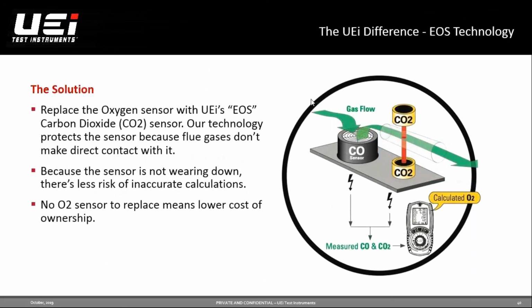So UEI decided there's got to be a better way to do this. Once again, you need two values, and you can extrapolate out the third. So UEI's engineers, who are way smarter than I am, came up with this idea called our EOS technology, our electrical optical sensor. What that does is give you a direct reading of the CO, then it takes the rest of the gases and passes it through a bit of an IR bench to give you your CO2 reading, and then it calculates out the oxygen. Now that's allowed us to have an analyzer that's not going to just randomly die on you, and it's also allowed for a lower cost of ownership.